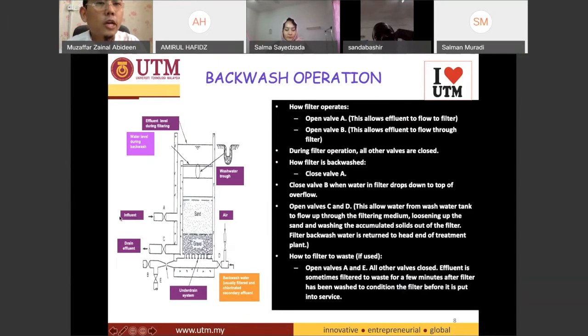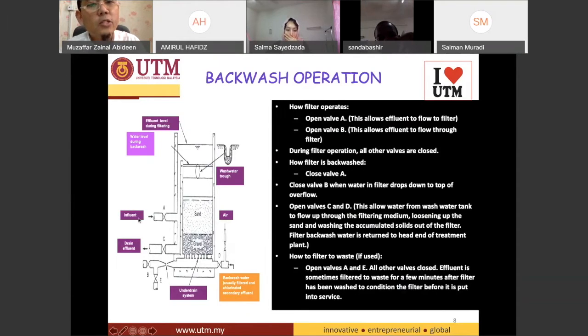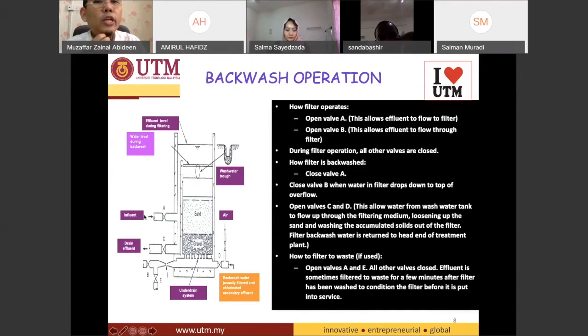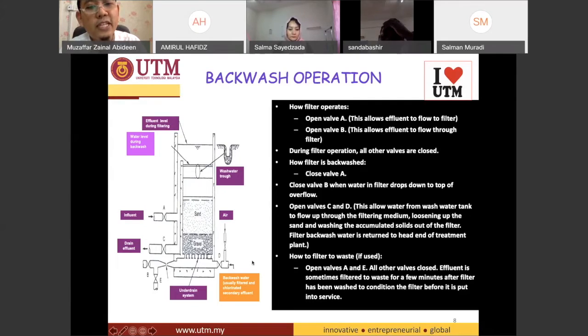The water from sedimentation will be entering valve A, so we have to open valve A. It will travel through the filtration and then go out at valve B. That means you have to open A and B while closing valve C, E, and D. During the normal filtration, we also keep a little bit of water at valve D.